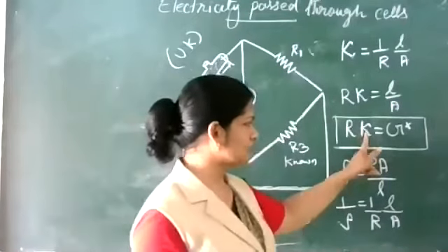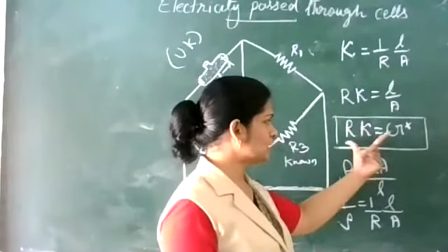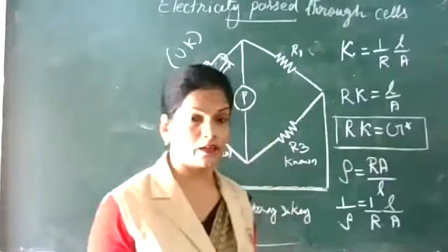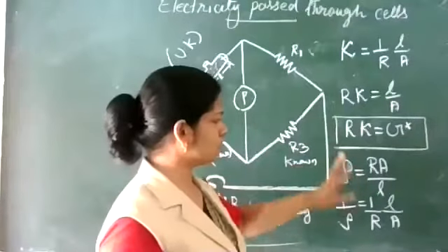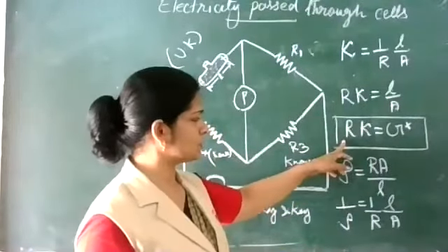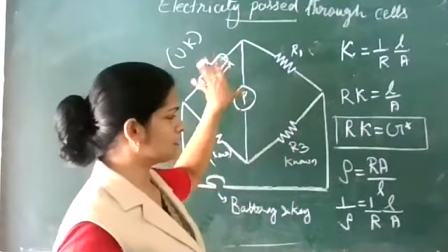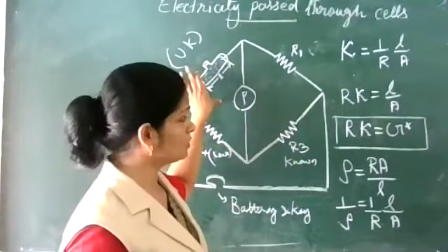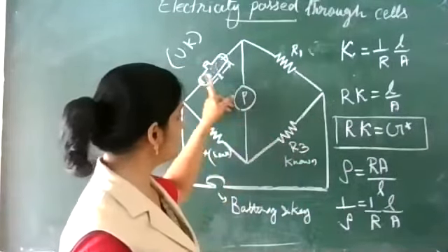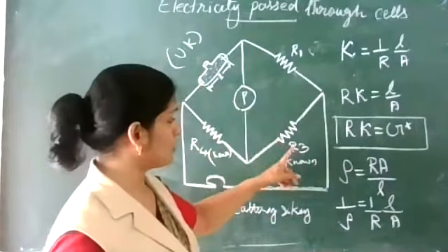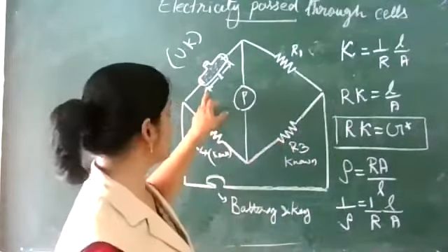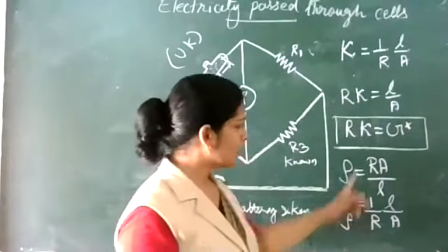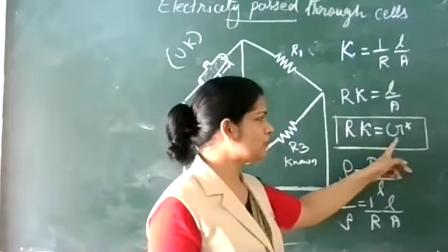To find out this conductivity kappa, two things you need to know: one is the resistance and the other is the cell constant. How can you find out the resistance of the solution? Of course, you connect it in the resistance bridge. You can find out the resistance by using R1 R4 upon R3. That is how you are going to get the resistance. So resistance is available here. Kappa you will be finding out, so you need what? G star.